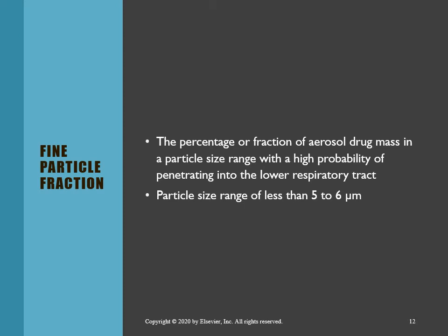Let's talk a little more about fine particle fraction. This is the percentage or fraction of an aerosol drug mass in a particle size range with a high probability of penetrating into the lower respiratory tract. So what is that particle size range that gets into the lower respiratory tract? Particles that are 5 to 6 microns in size will get into that lower tract.